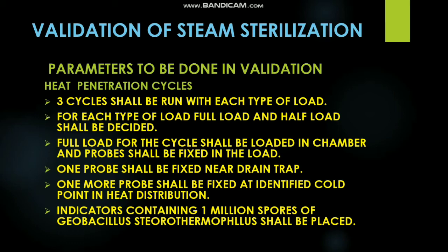So first we need to decide the load, and first we need to decide the maximum load, that is, what maximum load can be placed inside your steam sterilizer. So 2 things shall be decided before starting this study: what should be the maximum load and how it will be loaded, what should be the loading pattern. Both of these are very important in heat penetration studies.